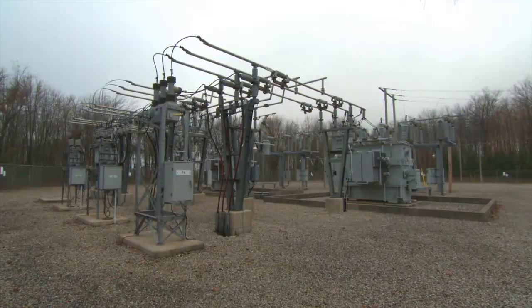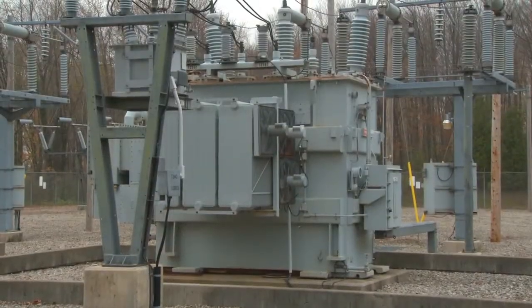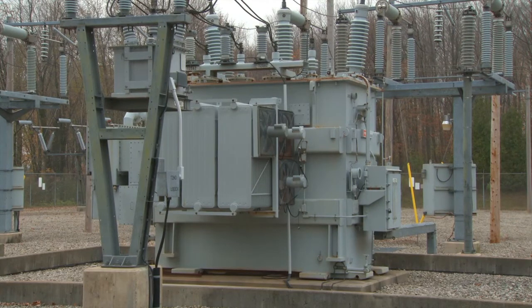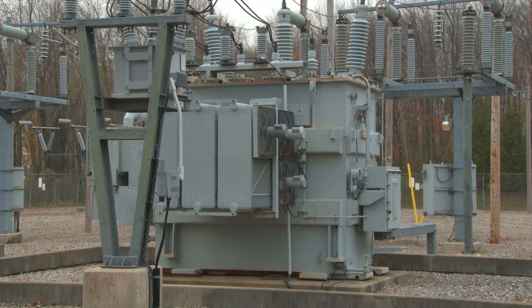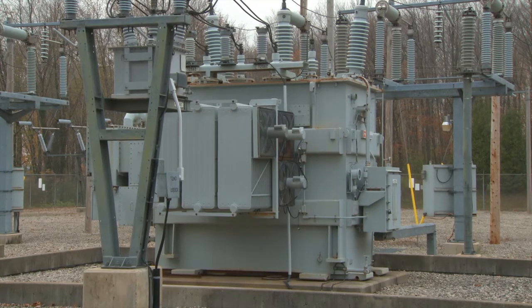If the internal electrical insulation systems break down, then the transformer life can be shortened significantly, and that has negative service and cost implications. A dry transformer can last decades longer than one with unacceptable moisture leaks. In the simplest of terms, water within a transformer needs to be minimized if the service provider wants to maximize service and equipment life. The water within a transformer equilibrates itself between the oil and the insulation paper, with 99% of the moisture residing in the paper.